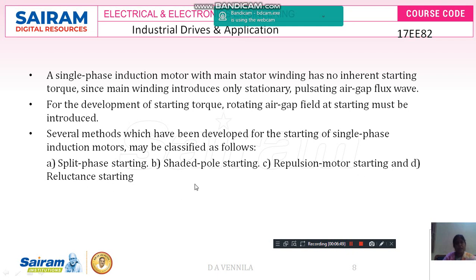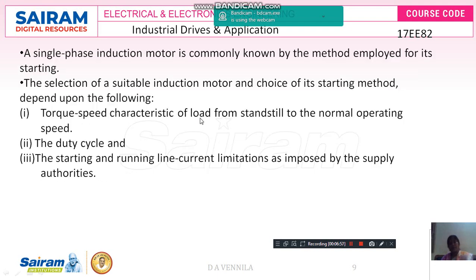The single phase induction motor is commonly employed based on its starting method. The selection of the suitable motor and the choice of starting method depends upon three factors: first, the speed-torque characteristics of the load from standstill to normal operating speed; second, the duty cycle; and third, the starting and running line current limitations as imposed by the supply authorities.